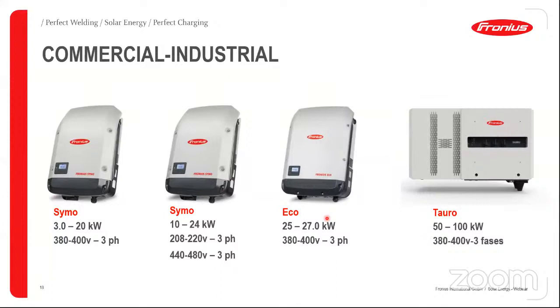In the Symo, same as in the Primo, depending on your country, you can have different power ranges or sizes in the output. In those countries with 50 hertz, or as we call it ROW, we have this three-phase inverter from 3 kilowatts to 20 kilowatts. And if you see, the voltage is from 380 to 400 volts. In the 60 hertz market, or the UL market, we have these three-phase inverters from 10 kilowatts up to 24 kilowatts. And we have two different voltages for these inverters, 208 and 480. So it also depends on your requirement.